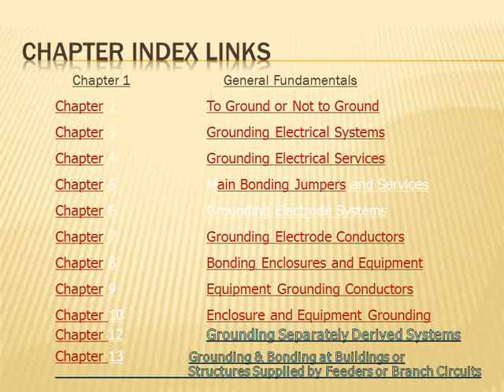To understand grounding and bonding, here's your transformer. Do you want to ground the transformer or not? Yes, let's ground it. Now you are dealing with a grounded system. Here's your service coming to your building. You take your conductors from the grounded transformer, and now you're dealing with a grounded system into your service panel. The transformer is already grounded, but right at the first panel you also need to ground the system again. When you bring in your neutral, you bring a grounding electrode conductor in the first panel, tie it to the steel of the building and to all the grounding electrode system, and tie it to the neutral.